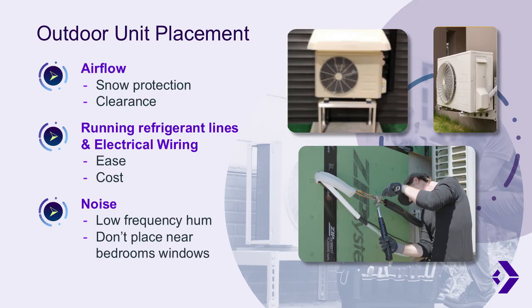Third, refrigerant line and electrical wiring. Think about cost and ease of installation. A great spot for outdoor equipment doesn't help much if it requires running 60 feet of line set through unnavigable house framing. Straightforward routing keeps the install time down, reduces chances for leaks, and keeps the job cost effective. Finally, noise. These units are quiet, but they're not silent. Placing a unit outside a bedroom window can lead to noise complaints due to low-frequency hum. Thoughtful placement can avoid these issues.